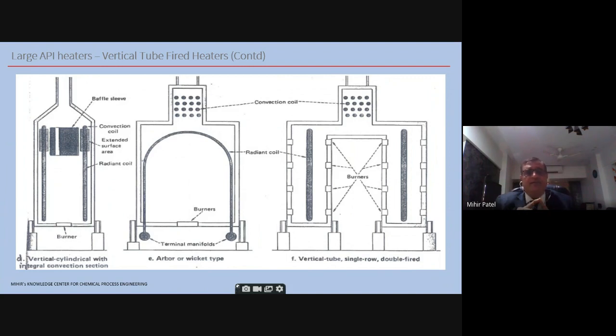You always have to remember that with the original burners, which were there maybe 40-50 years back, the flame length was a certain length. Ultra low NOx burners, which are predominant now, have a flame length 2 to 2.5 times that. That is why, for the design aspect, it is best left to the OEM, because the burner flame and all is very important in this.